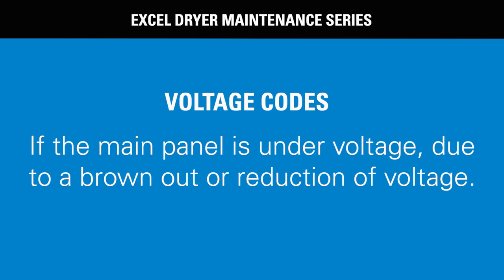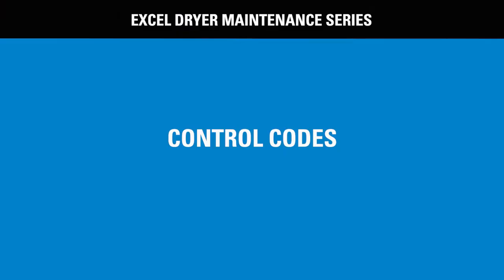If the main panel is under voltage due to a brownout or reduction of voltage, there will be a code flash of 3 long and 4 short. Again, check incoming voltage and try resetting the circuit breaker. Control codes. You may receive a code flash of 4 long and 3 short. This signifies a control is over temperature. Reset the circuit breaker to clear the code. If it still will not start, replace the control assembly.